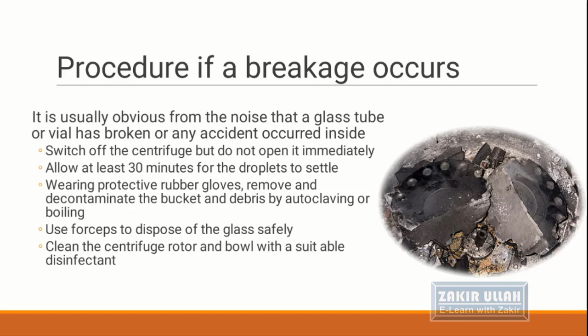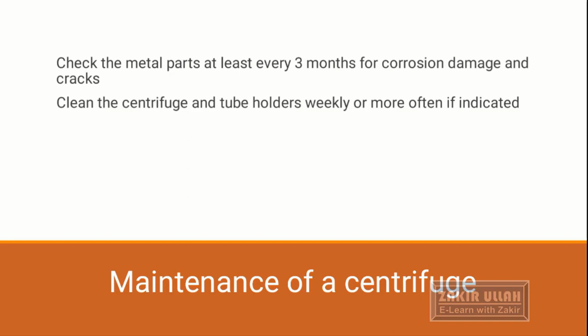How to maintain a centrifuge? These are certain points which we have to learn. Check the metal parts every 3 months for corrosion damage or cracks. Check all the parts after 3 months for these things. Then clean the centrifuge and tube holders. Try to clean it weekly, or depending on your workload, that is, how much workload there is in your lab. If the workload increases, we have to clean our centrifuge after 2 days, 3 days, or 2 times in a week, or at least 1 time in a week. We should clean all these tube holders and the inside parts of the centrifuge.